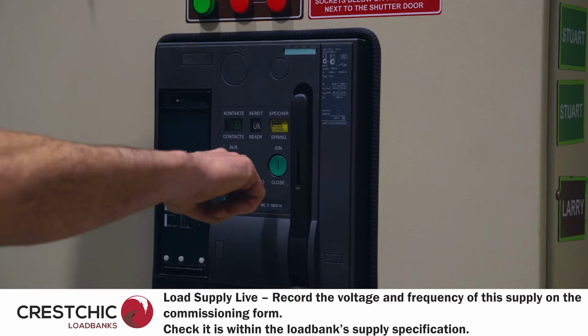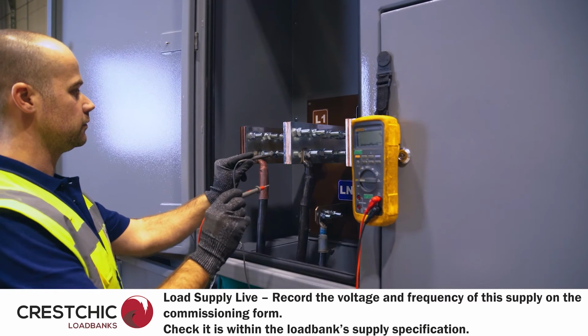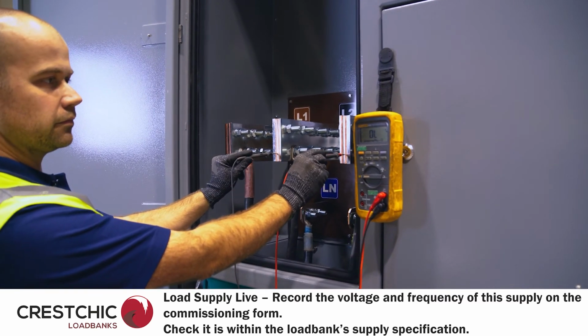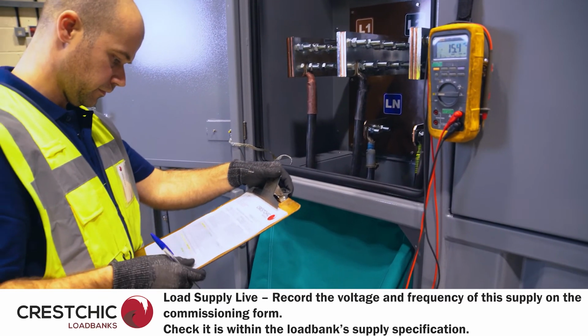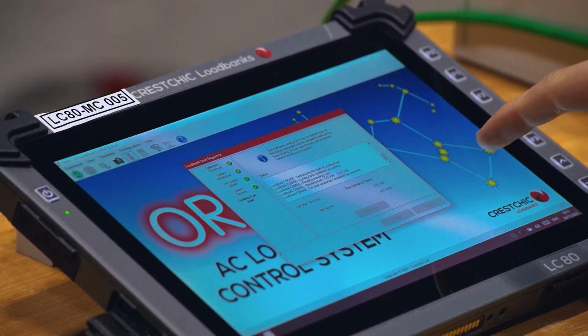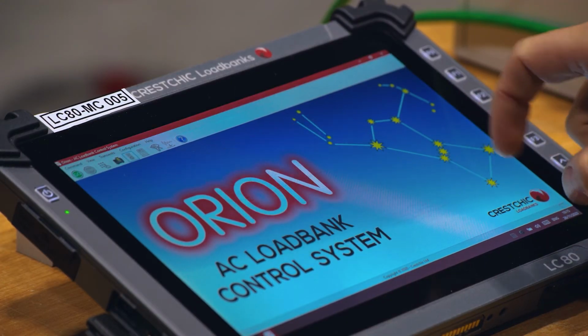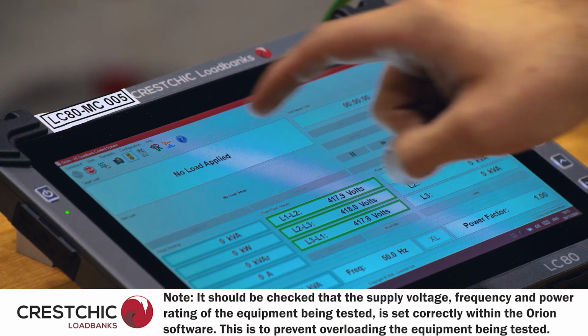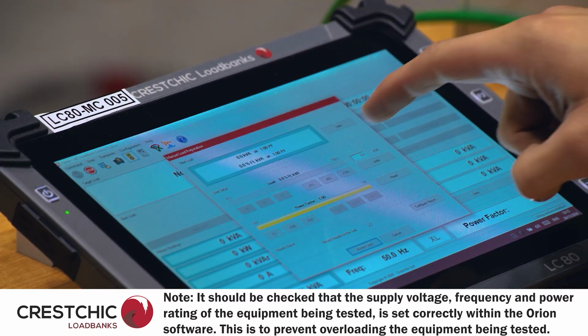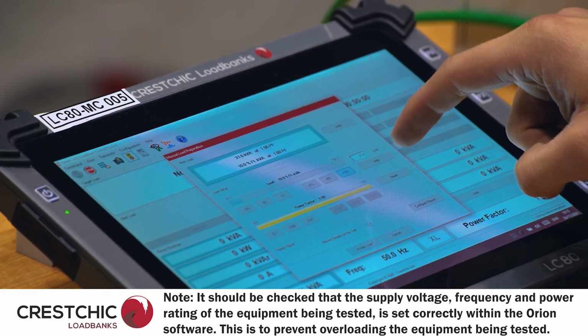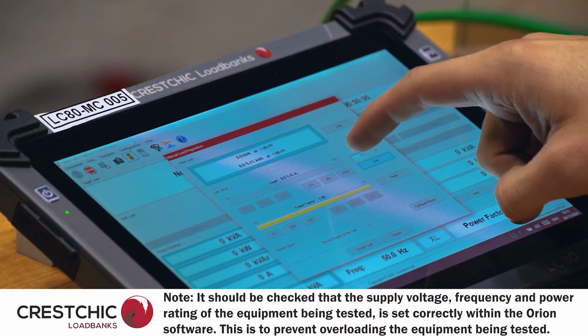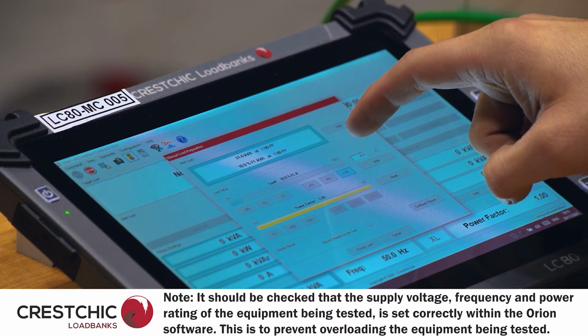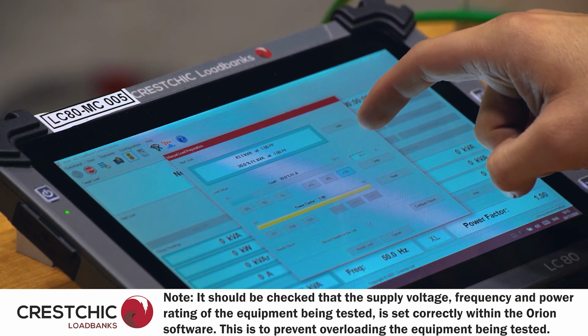The load supply can now be turned on. The voltage and frequency should be checked and recorded on the commissioning form. Now we have a supply from our load supply source, we can apply some loads. It should be checked that the supply voltage, frequency and power ratings of the equipment being tested is set correctly within the Orion software. This is to prevent overloading the equipment being tested.